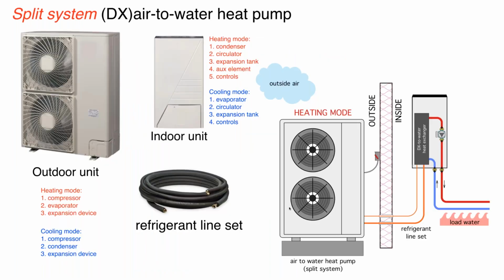A third variation is a split system. This is typical residential air conditioning, where we have an outdoor unit, an indoor unit, and a refrigerant line set running between them. The outdoor unit typically comes with a refrigerant charge sufficient up to a certain number of feet of line set, but the installer does have to connect the line set, provide a pressure test, pull the vacuum on the line set, and then open the service valves in the outdoor unit and allow the refrigerant to go through the system.